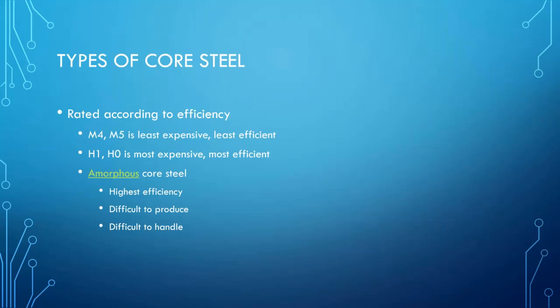There are different types of core steel used in the transformer construction process. When they're purchased by the transformer manufacturer, they are rated by efficiency. So there's M4, M5 core steel. I don't think any transformer manufacturers are still using M5. I believe with the DOE standards that came about in 2016, everyone was forced to go to M4 or a greater efficiency. There are core steels rated with H's, H1, H0.